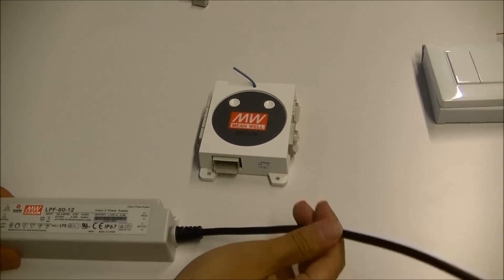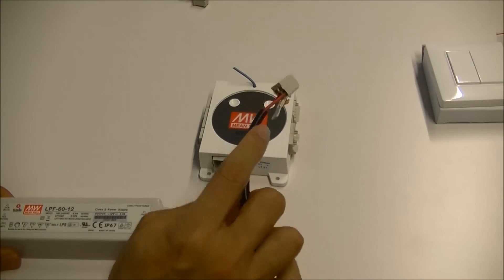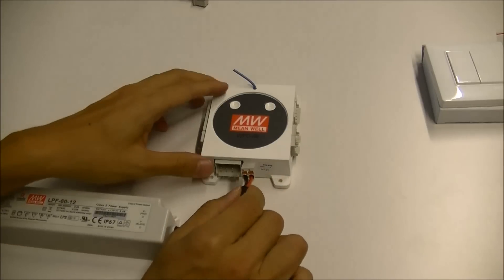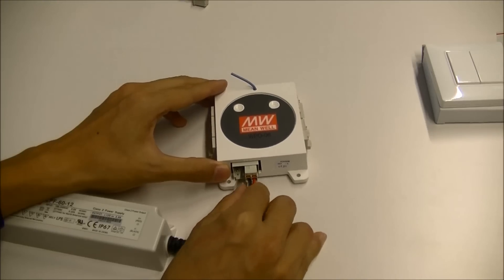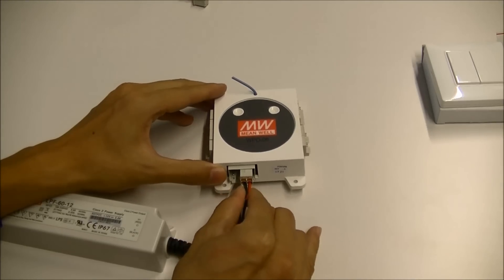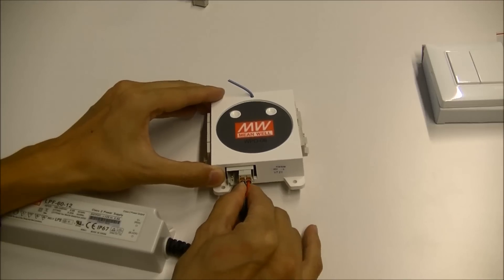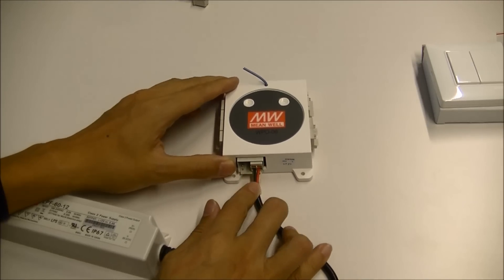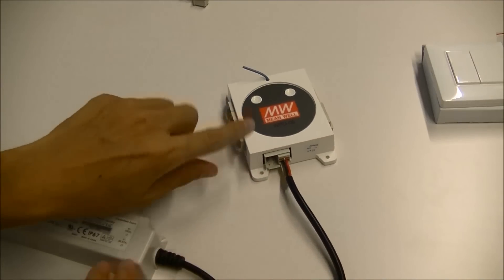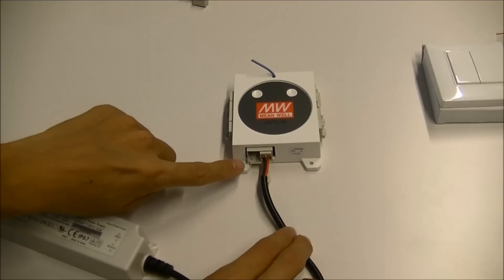First, push the plug from LED driver into the input of dimmer. You will hear a click sound in case the plug is pushed in correctly. If the total current is higher than 16 amperes, it is necessary to have another plug at the input.